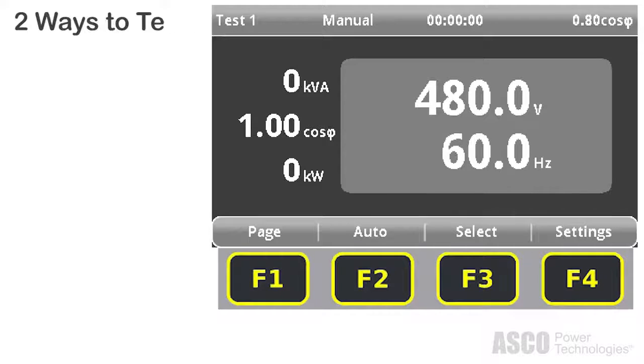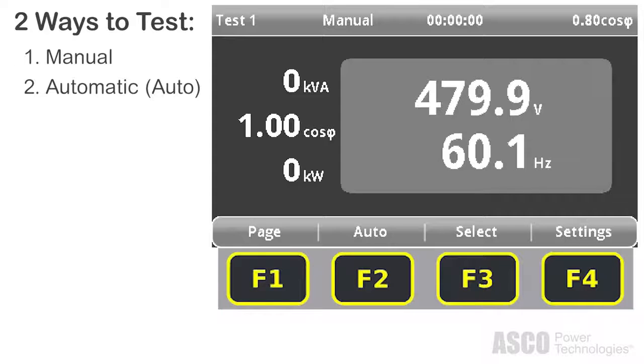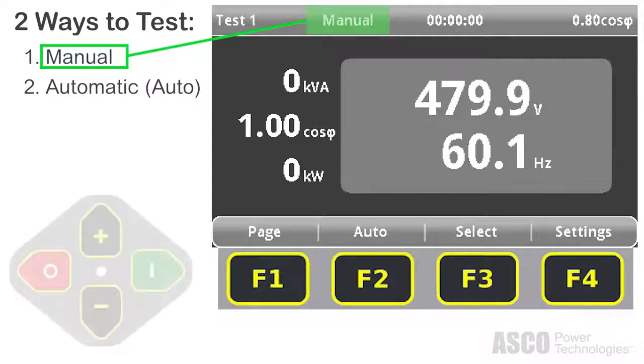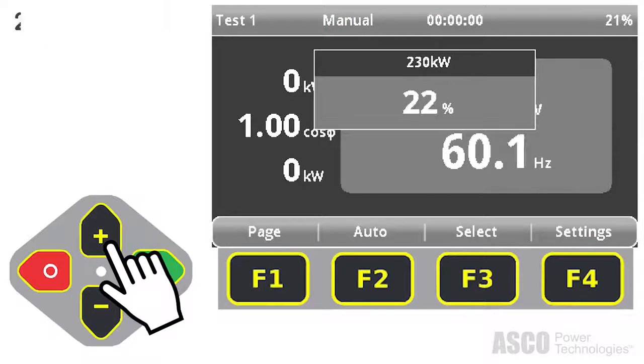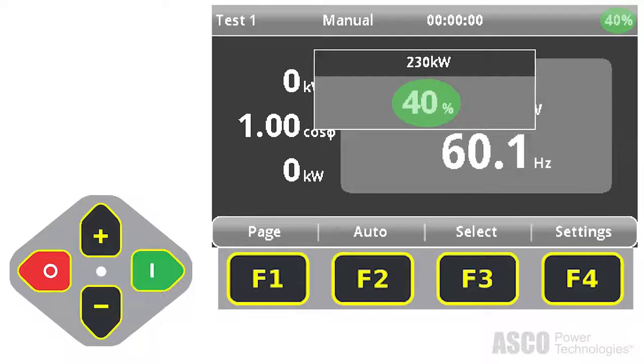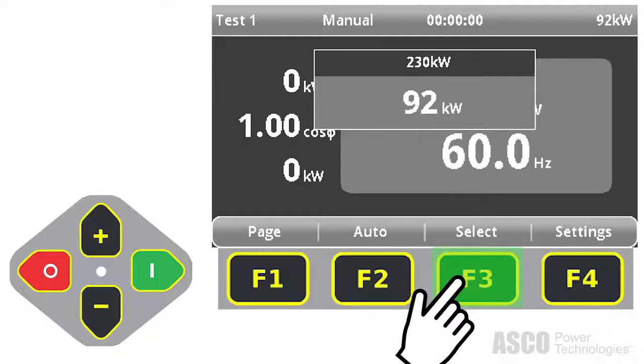Now there are 2 ways to test your load bank, manual and auto. We're going to start with manual. You'll notice what mode you're in by up here. So to do manual, all you do is hit the increase or decrease buttons and it'll show up here, we have a percentage. But if you'd like to work in kilowatts, you hit the select button. It will show the kilowatts. If you hit it again, it'll show power factor. So you have 3 ways to apply load.